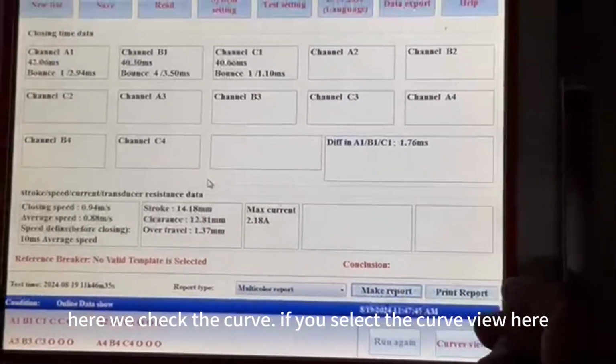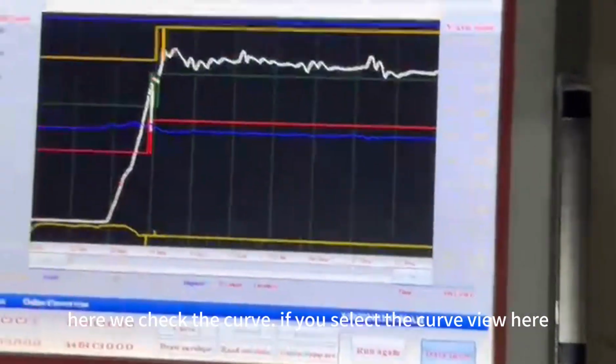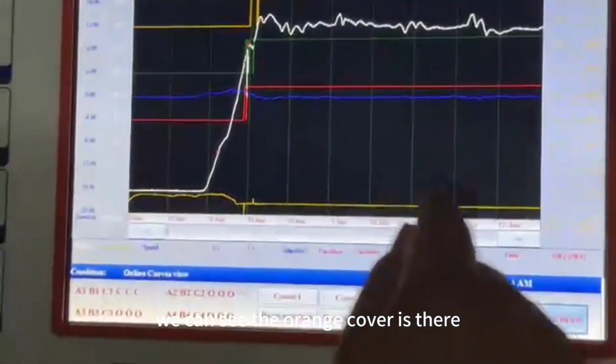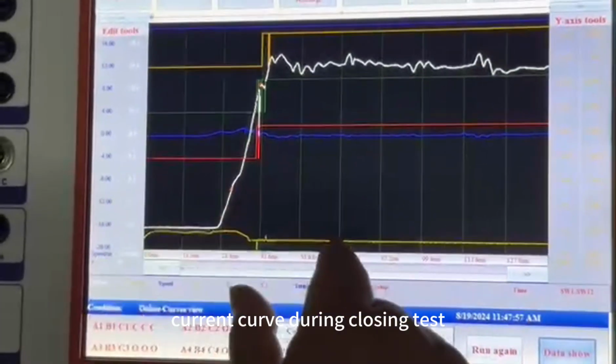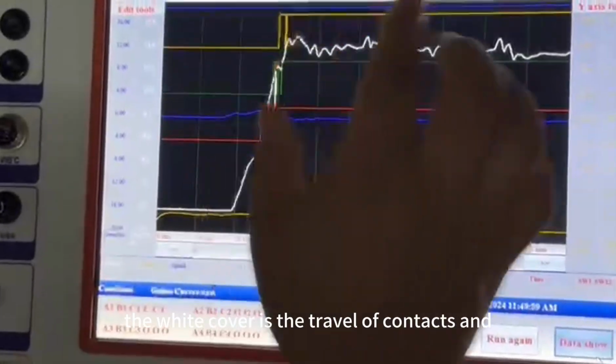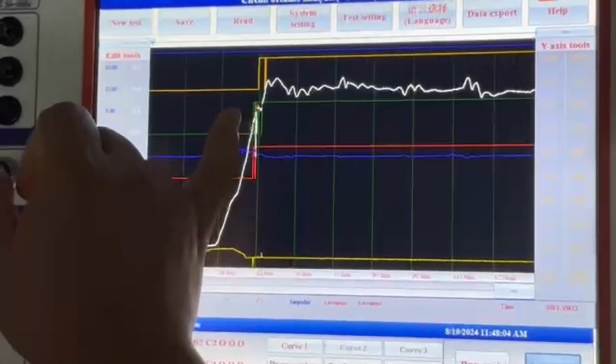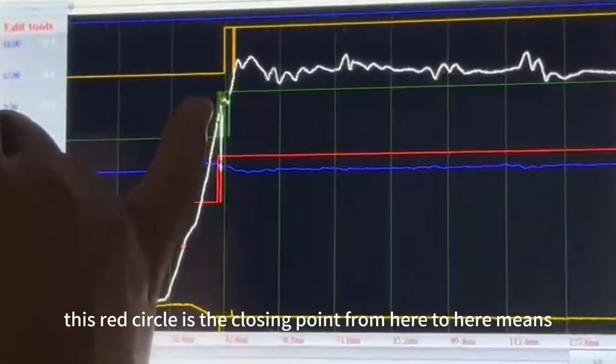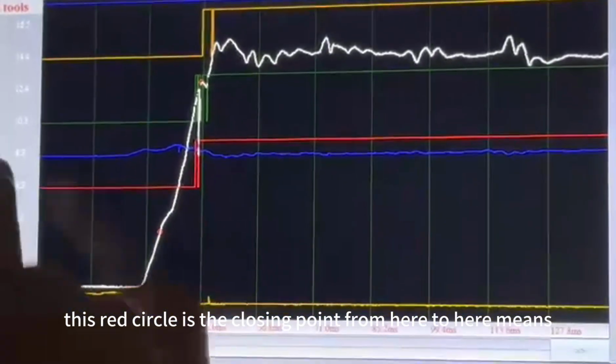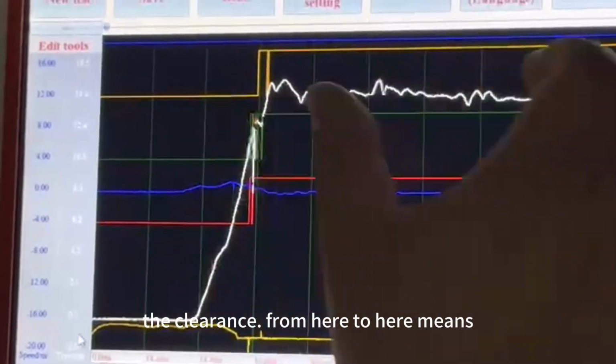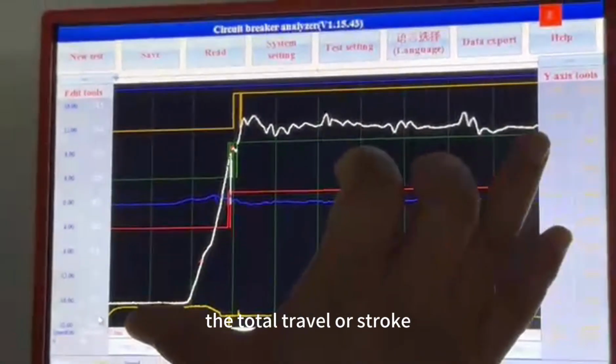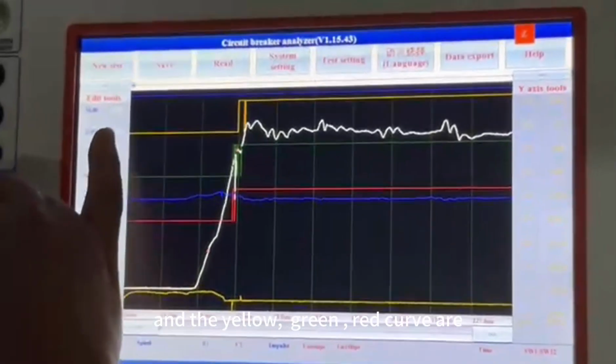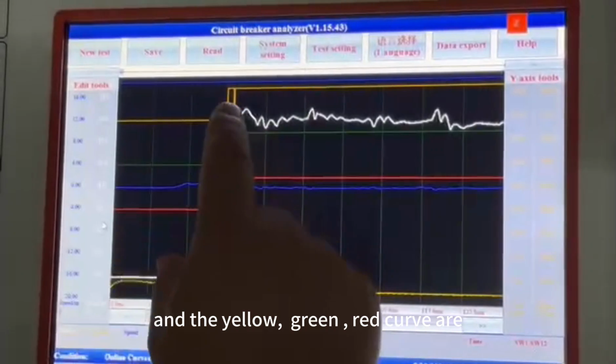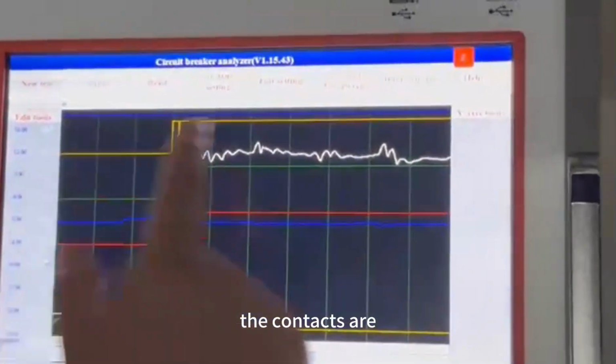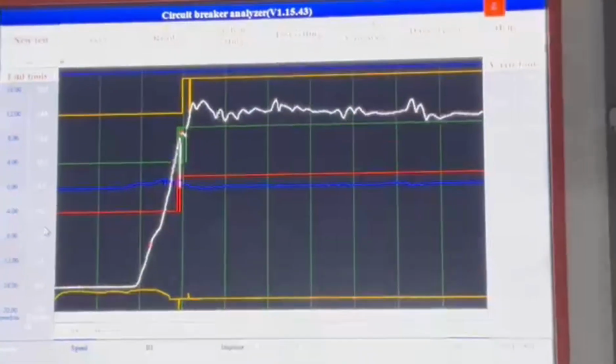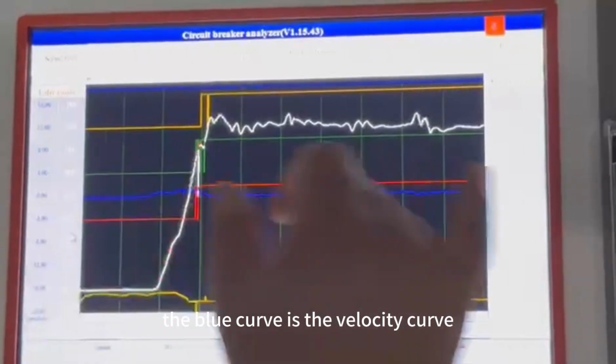Here we check the curve. If you select the curve view, here we can see the orange curve is the current curve during the closing test. The white curve is the travel, and this red circle is the closing point. From here to here means the contact travel. From here to here means over travel. From here to here means the total travel or stroke. And the yellow, green, red curve is the contact states. The blue curve is the velocity curve.